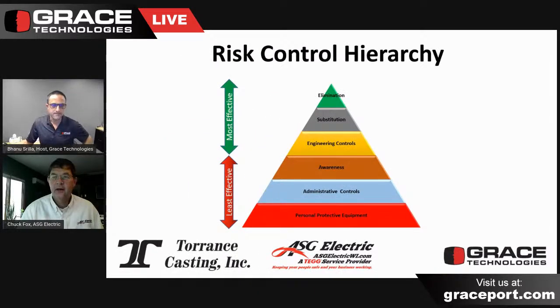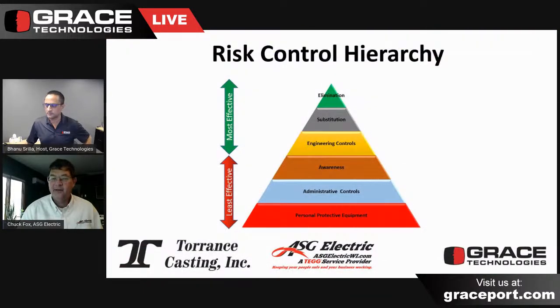Throughout the process, 70E has been our guide. Once we know we have this cabinet of 119 calories, and that the customer wants to access it for maintenance and inspections, how do we get there? 70E gives us guidelines under Article 105.4: hazard elimination shall be the first priority. And in the 2018 standard, what's new is the chart on your screen outlining the standards of the risk assessment protocols.